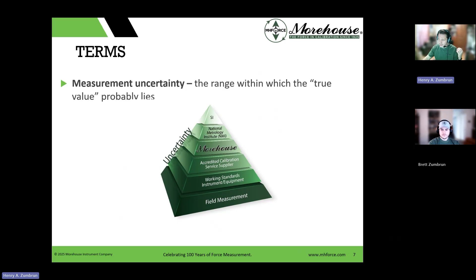The general GUM, Guide to the Expression of Uncertainty in Measurement: it's repeatability, resolution, reproducibility, reference standard uncertainty, reference standard stability, environmental factors, and other. So Brett, you know why I put other here? I can't say. Because this is your catch-all, so no one can yell at you and say these are wrong and you missed out transport uncertainties, you missed this, you missed anything else. You can basically say it's under other, but we have our 5 R's and our E, and then, of course, depending on the instrumentation and what you do, there could be other things that impact.